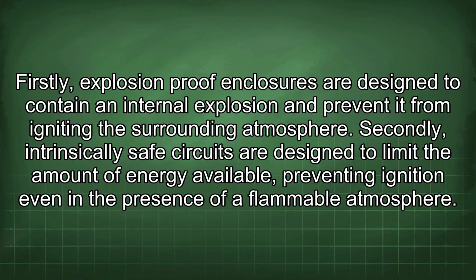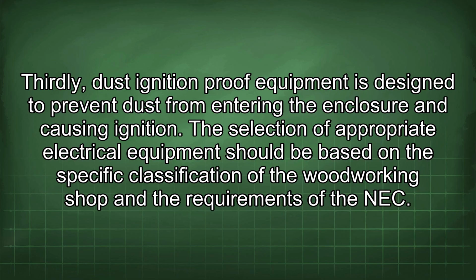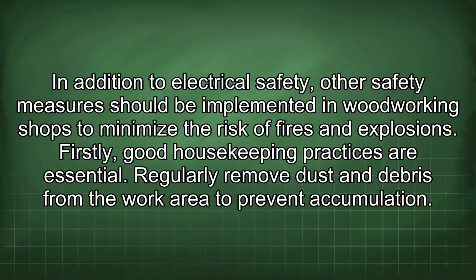Secondly, intrinsically safe circuits are designed to limit the amount of energy available, preventing ignition even in the presence of a flammable atmosphere. Thirdly, dust ignition-proof equipment is designed to prevent dust from entering the enclosure and causing ignition. The selection of appropriate electrical equipment should be based on the specific classification of the woodworking shop and the requirements of the NEC. In addition to electrical safety, other safety measures should be implemented in woodworking shops to minimize the risk of fires and explosions.